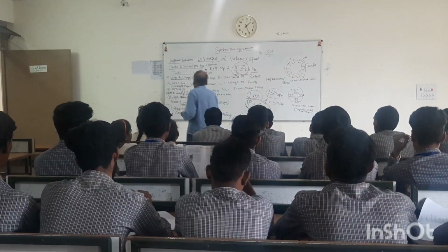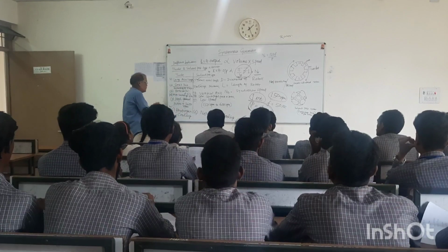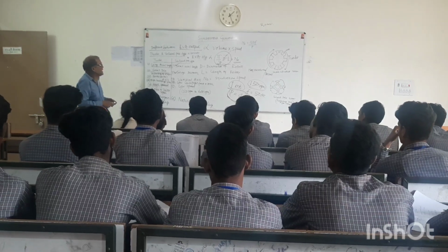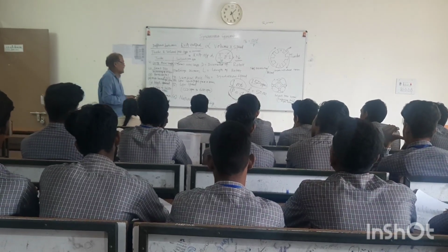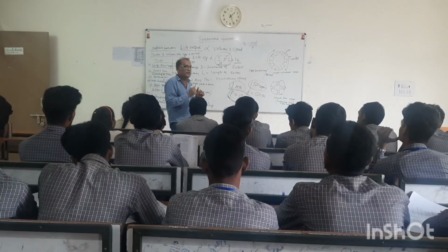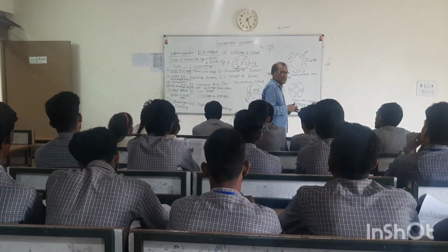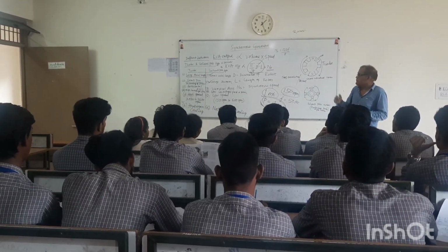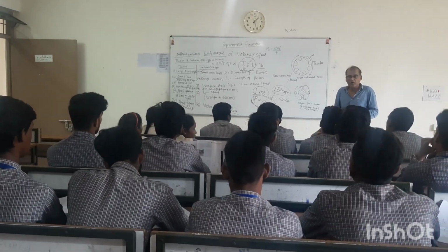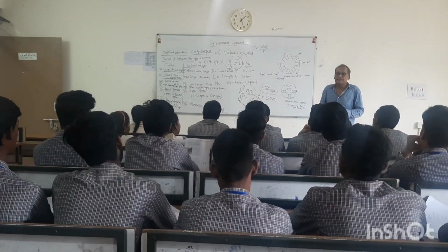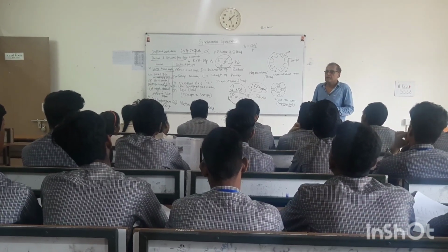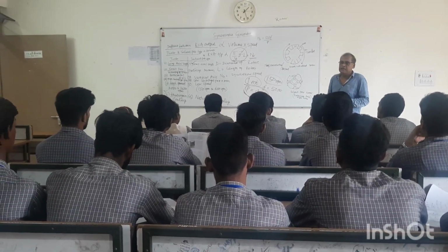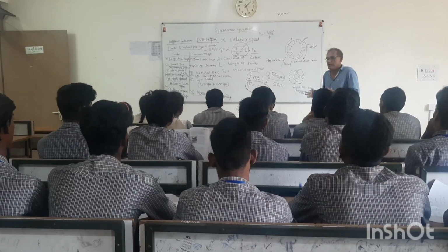We adopt hydrogen cooling for turbo alternators, whereas in the case of salient pole or hydroelectric alternators, natural air cooling will be sufficient. In cost comparison, the cost of a turbo alternator will be more as compared to the salient pole alternator. So that is the basic difference between salient pole and turbo alternators.